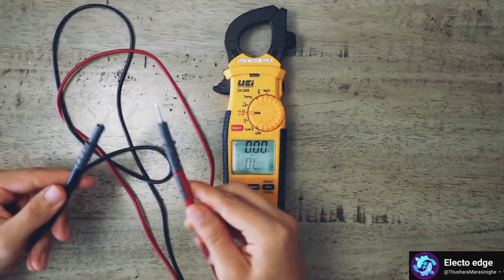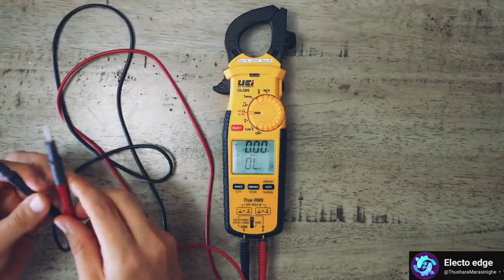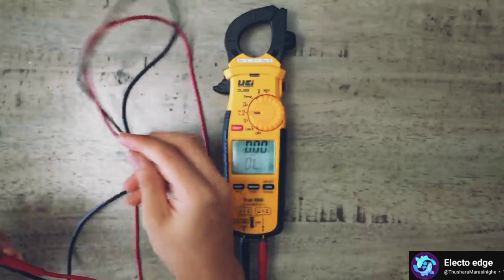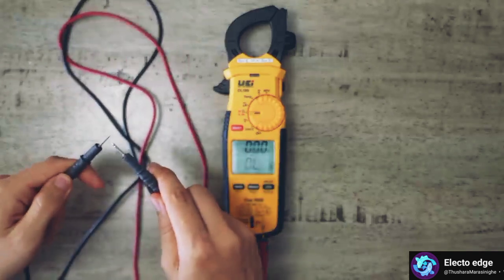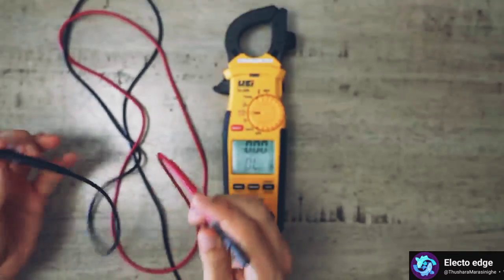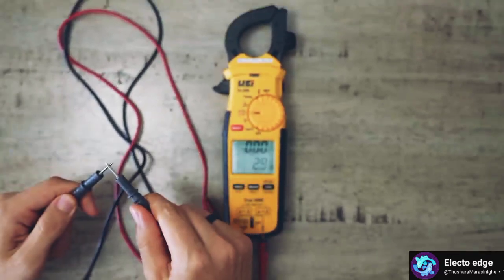The continuity setting is also a great way to check to make sure that your meter leads are good and there's no breaks in the wires. If you just touch the 2 leads together, you should get a beep. If it's not beeping, then you know that the wire is broken on one of the leads.